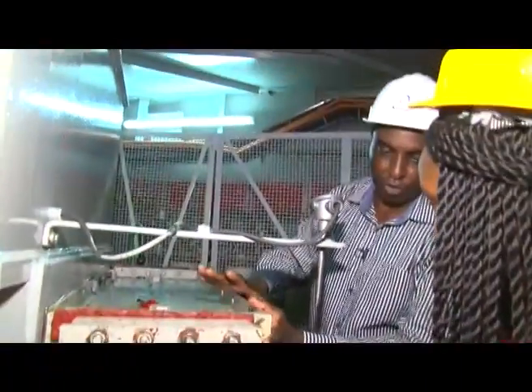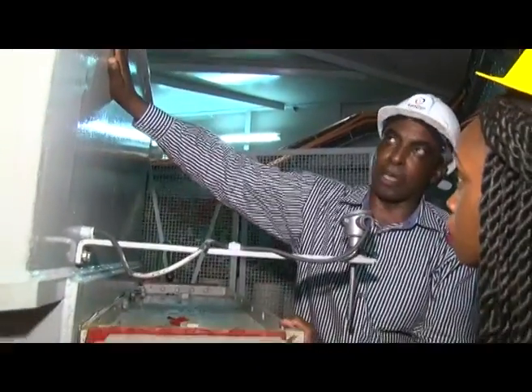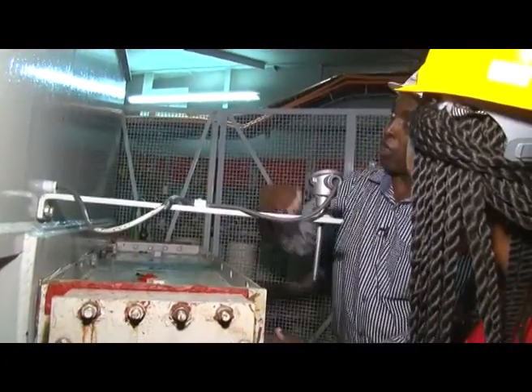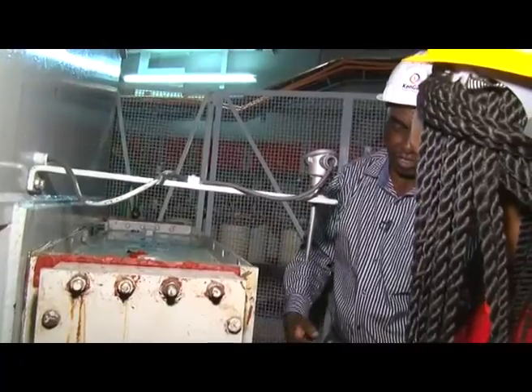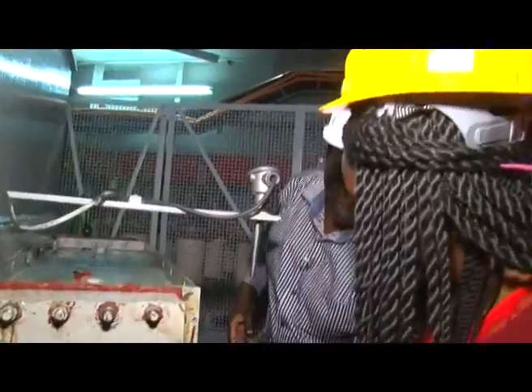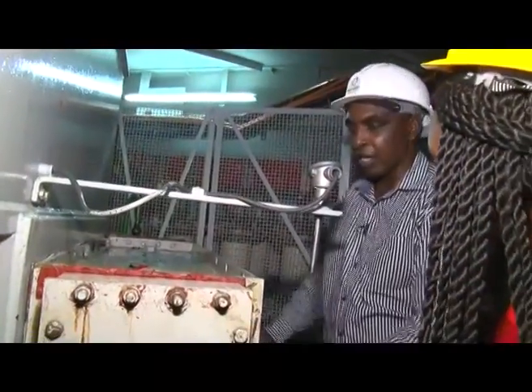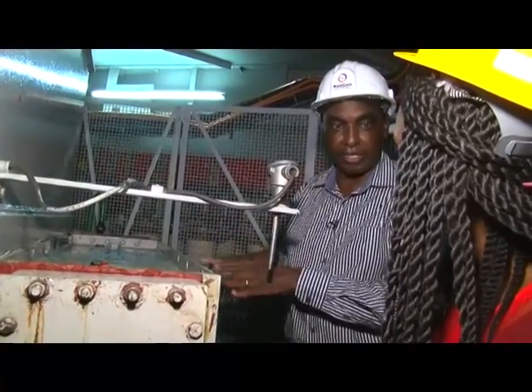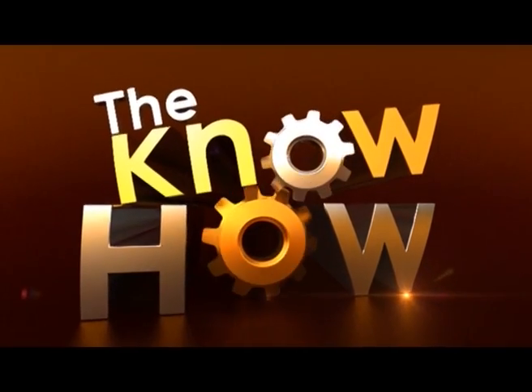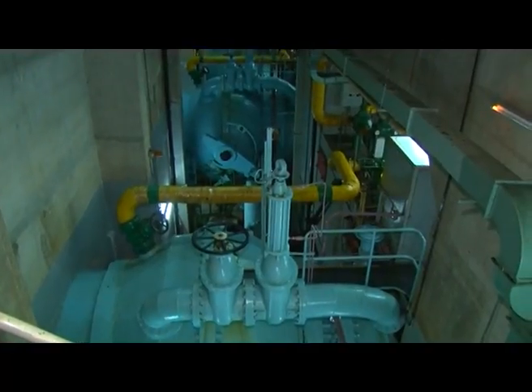These are the radiators I am talking about for the cooling. This is the stator — the cables are inside. There is an opening here so as it rotates it forces the air out, it circulates air, and the air goes out because the housing is closed. This one passes cold water, so as the cold water passes it cools that air and keeps the air cool. This is the water coming in from the dam — we will see where it goes to the machine.